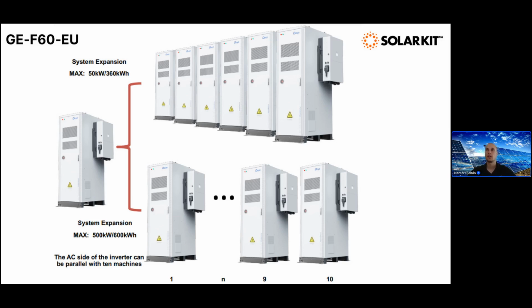But if you would like to expand the AC power of the batteries too for the whole system, you can connect 10 pieces of these GE-F60 together, then you would have 0.5 megawatt of AC power and 600 kilowatt hour of battery capacity. So this way you can reach larger AC output and also expand the capacity you have for the ESS. And no extra devices are needed to connect them in parallel. You can just wire them together from inverter to inverter.